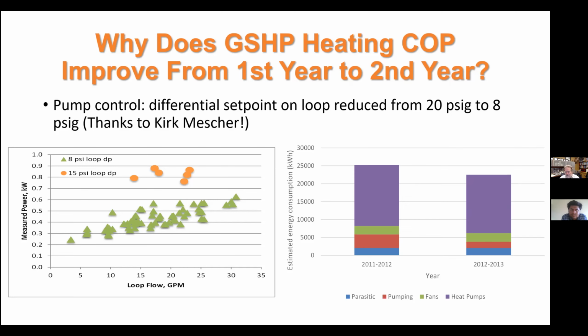We went there in, I think it was 2014 actually, and with some help from an electrical engineer from Southern Company, we made some measurements. We changed the set point to 8. I don't remember why we had 15 instead of 20, but that's what we had. And then we tracked it as the flows changed. You could see at 8, we're using somewhere between around 300 watts and maybe 600 watts, and at 15, we're using more like 800 to 900 watts. So, of course, if you increase the flow by increasing the pressure differential set point, you will make the heat pumps a little bit more efficient, but you're then also spending more electrical energy on pumping.